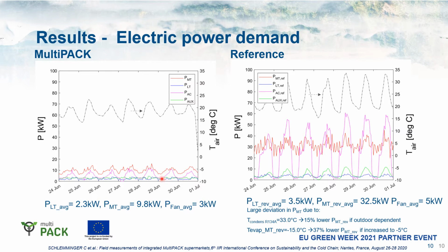What we see as a bigger difference is the electric energy consumption of the MT compressors. This is in the order of 10 kilowatt for the MultiPACK, while for the reference shop, we are in the order of 30 kilowatt. And the same, we see also that the power demand for the air conditioning is much higher for the reference shop than for the MultiPACK unit.